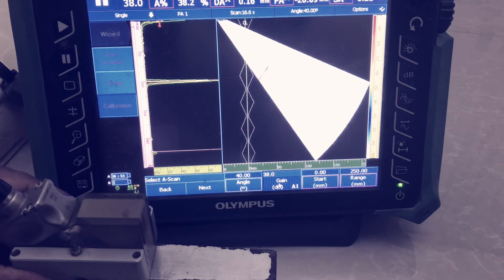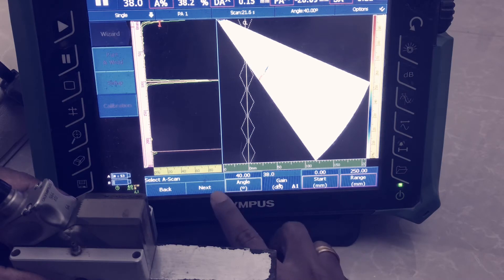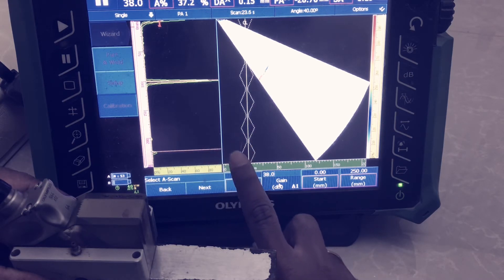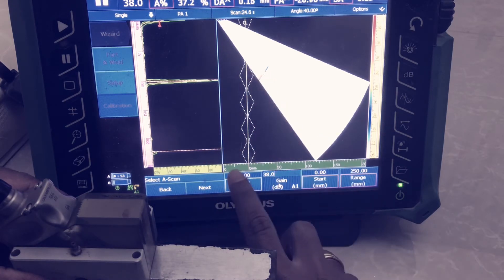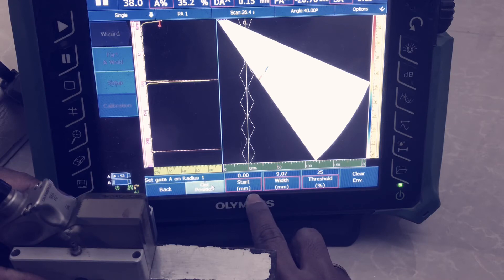Check the second echo also, it's coming or not. So increase the dB. Now it is coming. You have to take maximum amplitude. We have to take maximum amplitude, this is the maximum amplitude of this echo.